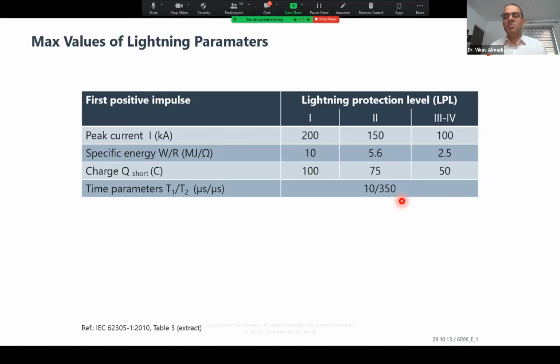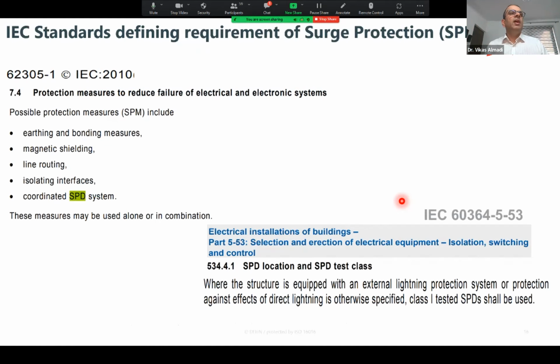So when I talk about surge protection, you have to consider both big and small kinds of surges which can disrupt the services. And even if you see the standard 62305, they talk very clearly about the coordinated SPD system, which many of us are avoiding. And a structure which has lightning protection, good or bad, doesn't matter, has to have a class 1 SPD. This is actually a requirement. Why it is a requirement, you will see.